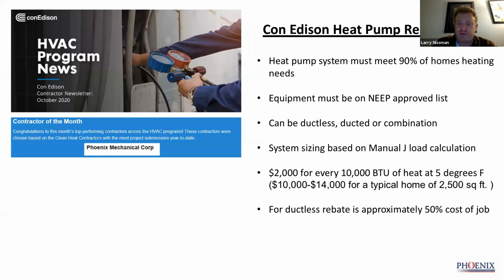The equipment must be on an approved list to verify its efficiency. As mentioned, the system can be ductless, ducted, or a combination—for example, a ducted system in the attic for the second floor and a wall mount on the first floor. We have to conduct a manual J load calculation to submit to Con Edison showing how many BTUs of heating and cooling you need for your house.